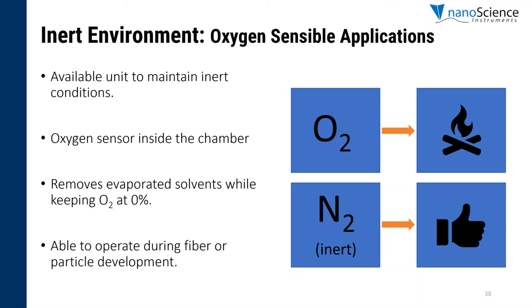This type of environment is ideal for applications like battery and energy storage where oxygen-sensible materials are needed. To maintain inert conditions, we also implement an oxygen sensor inside the chamber to make sure there's no oxygen flowing throughout the whole system. The unit also offers a condensing system to remove evaporated solvent from the inert gas, which is important as we can recycle the inert gas and keep these inert conditions cost-effective during sample development.